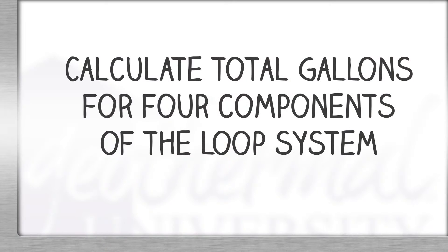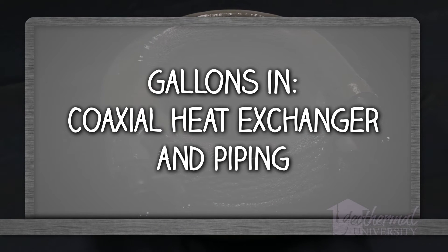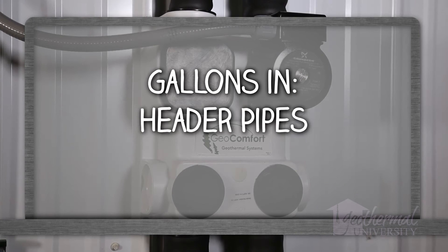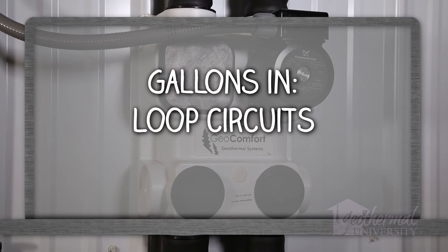We must calculate total gallons for four components in the loop system. They include gallons in the unit's coaxial heat exchanger and piping, gallons in the pump hose kit, gallons in the header pipe, gallons in the loop circuits.